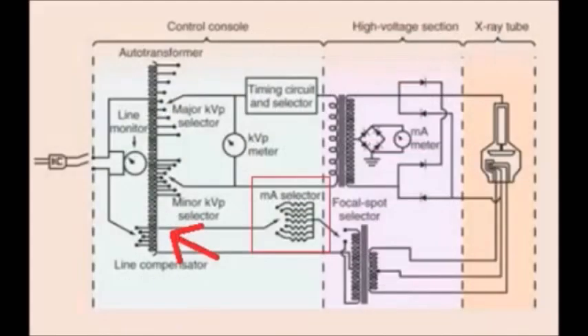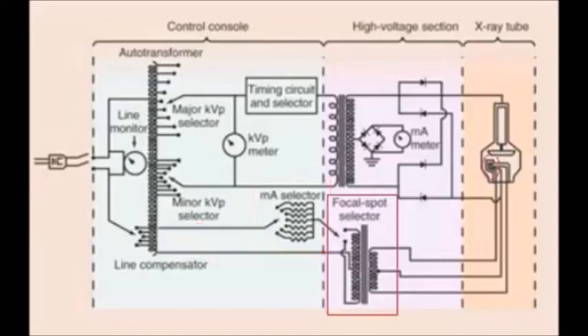Back to the auto transformer: on the filament circuit, secondary power from the auto transformer goes to the rheostat, which is an mA selector attached to the focal spot selector. Low mA associates with a small focal spot and high mA with a large focal spot. The step-down transformer reduces voltage from the rheostat before heating up the filament to create thermionic emission. Those electrons are fired off to the positively charged anode, creating bremsstrahlung and characteristic radiation.